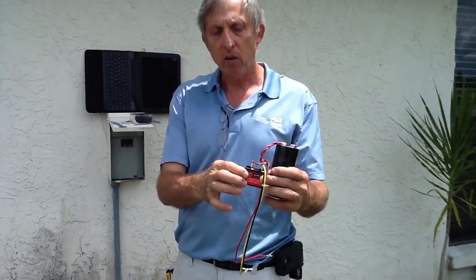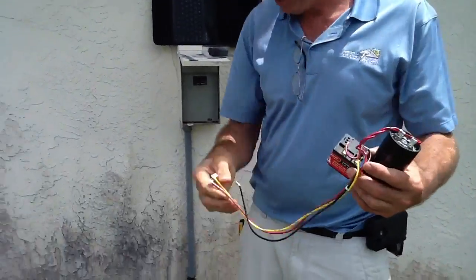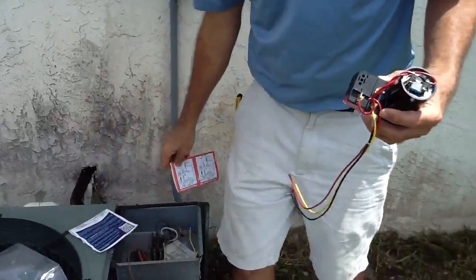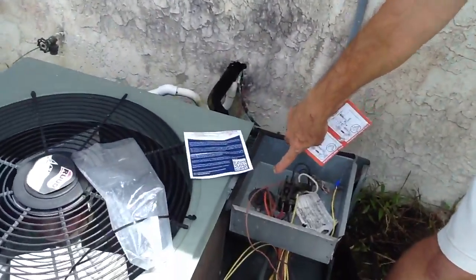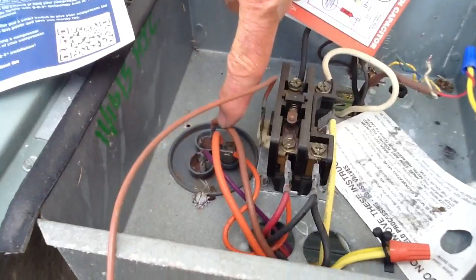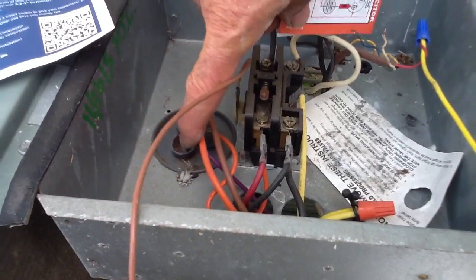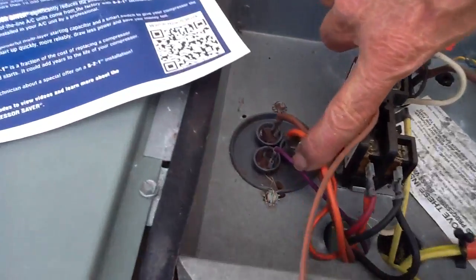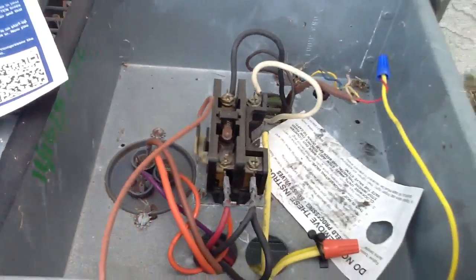That's where this hard start kit comes in. Now we've got three wires here, and I'll go over the diagram to show you what I'm talking about. As you look here, this is a dual capacitor system, which means we have the FAN part of the capacitor. The COMMON always has two wires on it, and this is the HERM — the HERM usually has one wire, and it could be an orange, purple, or red color.